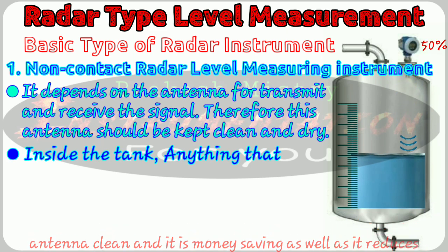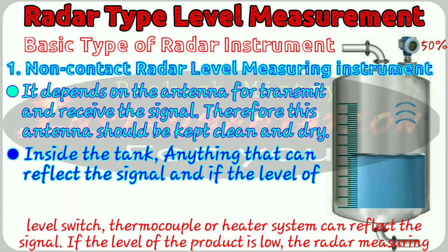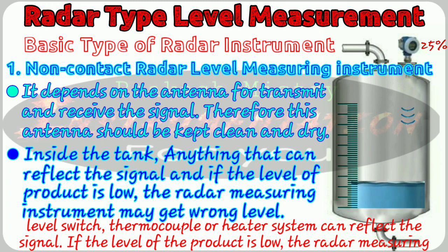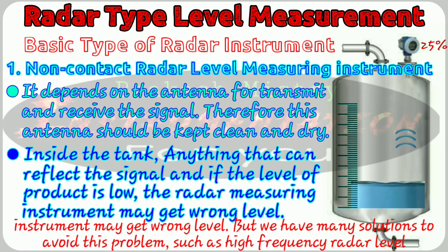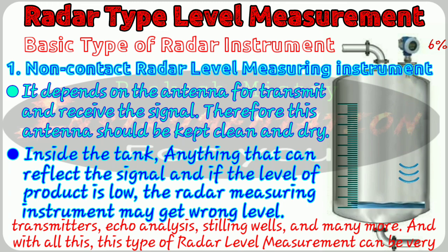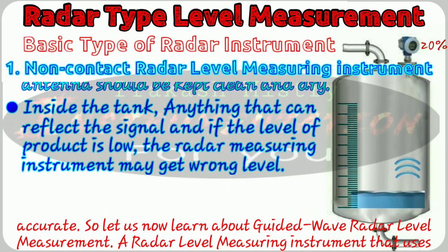Everything inside the tank such as level switches, thermocouples, or heater systems can reflect the signal. If the level of the product is low, the radar level measuring instrument may get a wrong level reading. But there are many solutions to avoid this problem, such as a high frequency radar level transmitter, echo analysis, stilling well, and many more. With all these solutions, this type of radar level measurement can be very accurate.